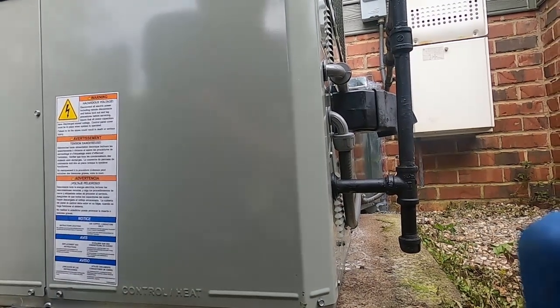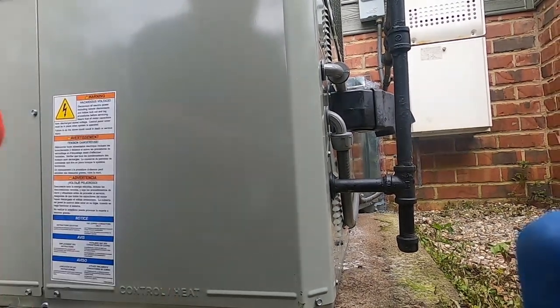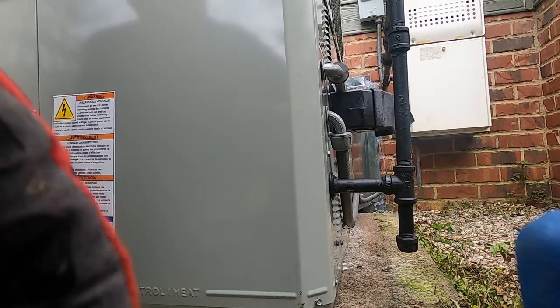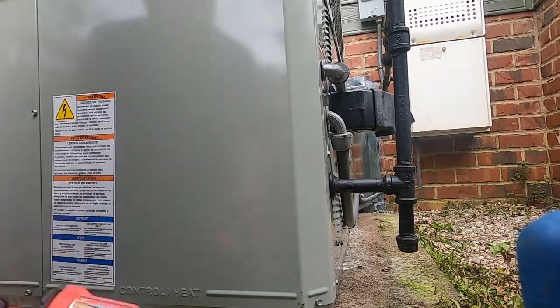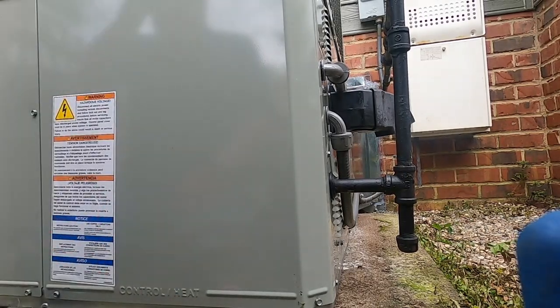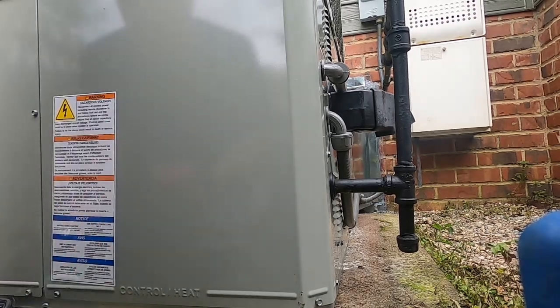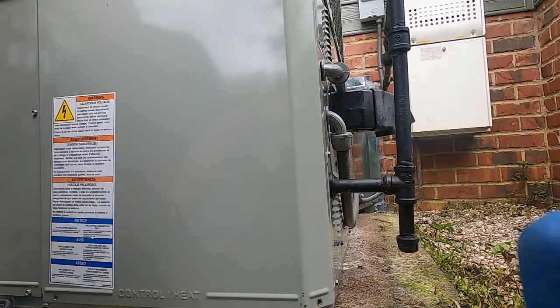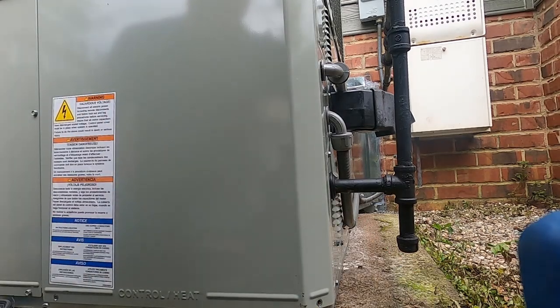So this is a Trane package unit we just put in this morning, and they had it pretty much swapped out by about 11 o'clock. There was one replacing one that we'd installed. It was about 3 or 4 years old. Had a micro channel coil in it. The micro channel coil sprung a leak right in the middle, and Trane cannot get a coil for it. So maybe after the first of the year, they're thinking, even if that.